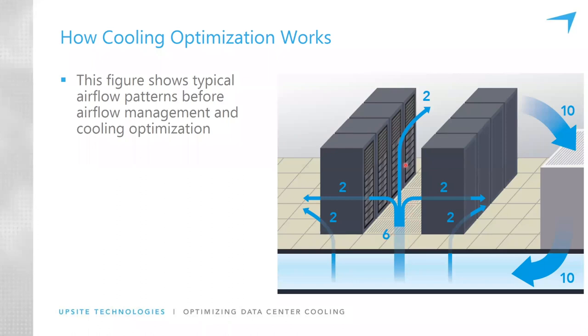When we look at the cold aisle, we see that all the IT equipment in this row of cabinets consumes 2 units of air. And this row also consumes 2 units of air. So the demand for the IT equipment is 4 units in this cold aisle, but we're delivering 6. That means there are 2 extra units of conditioned air delivered to this aisle that's not needed. That extra conditioned air leaves the aisle as bypass airflow, and we get our total of 10 units of air flowing back to the cooling unit.